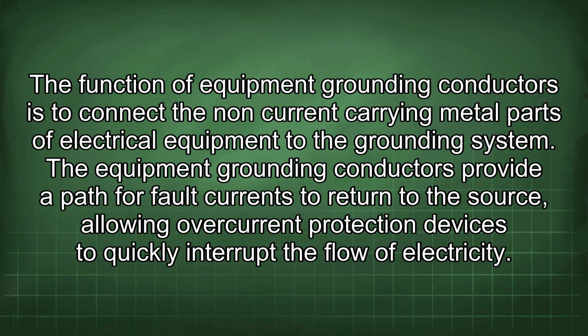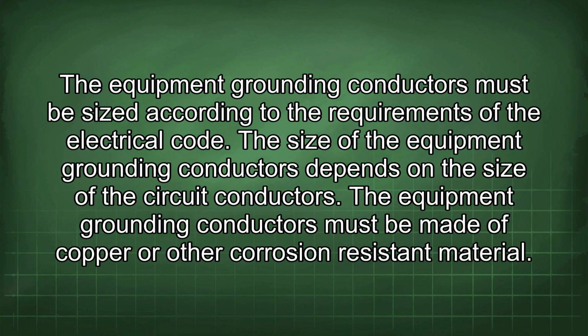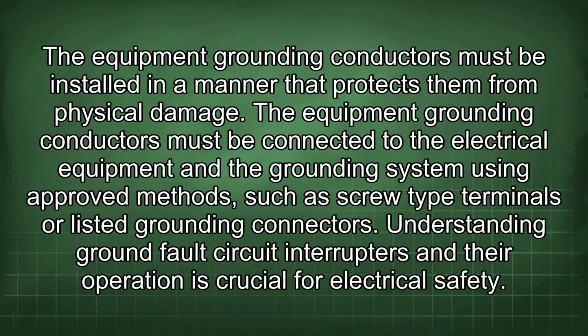The function of equipment grounding conductors is to connect the non-current carrying metal parts of electrical equipment to the grounding system. The equipment grounding conductors provide a path for fault currents to return to the source, allowing overcurrent protection devices to quickly interrupt the flow of electricity. The equipment grounding conductors must be sized according to the requirements of the electrical code. The size of the equipment grounding conductors depends on the size of the circuit conductors. The equipment grounding conductors must be made of copper or other corrosion-resistant material. The equipment grounding conductors must be installed in a manner that protects them from physical damage. The equipment grounding conductors must be connected to the electrical equipment and the grounding system using approved methods, such as screw-type terminals or listed grounding connectors.